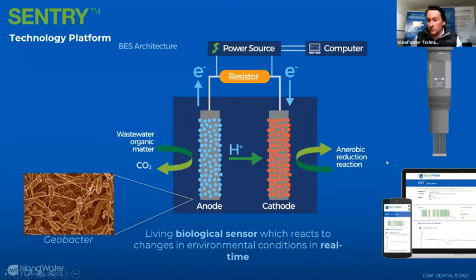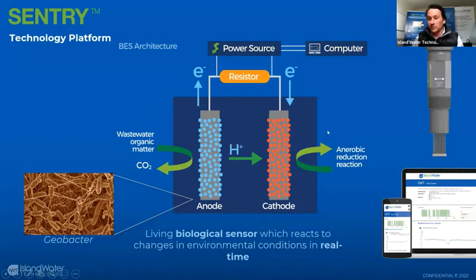In terms of the platform itself, we place physical sensors that look and feel like DO probes anywhere in your wastewater treatment process — from a collection system through influent monitoring, a primary clarifier, to the back end of aeration basins through to nutrient bioreactors. That information can go to a dashboard or via a 4 to 20 milliamp signal to an on-site SCADA.